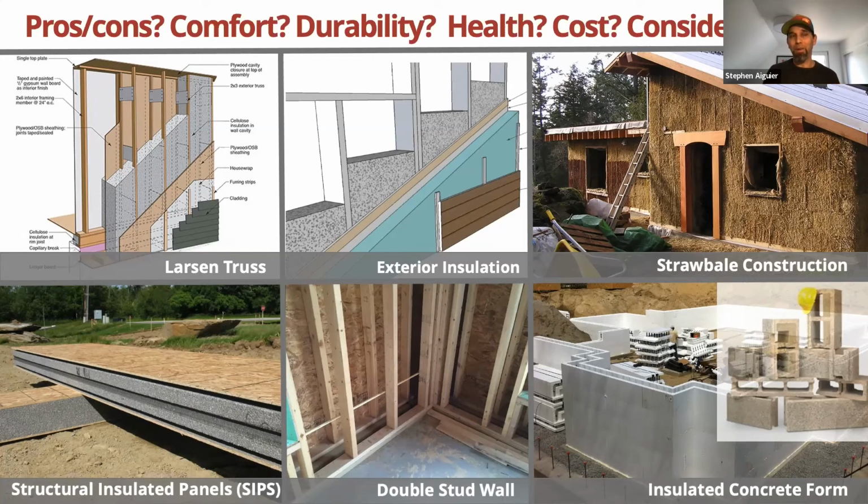One thing I forgot to mention is that relative humidity is really great between about 35% and 60% for humans. Ideal for human health is 50%. Buildings really want definitely no more than 60%, but ideally 50% or less. And so when you have good moisture batteries in the building, good storage, they tend to balance at that 50% mark pretty well if it's relatively airtight in a heating dominated climate like the Pacific Northwest.